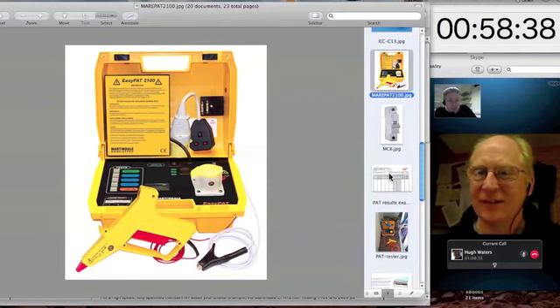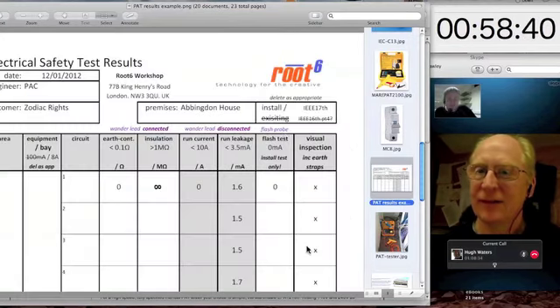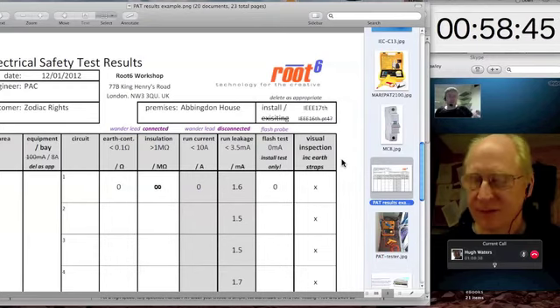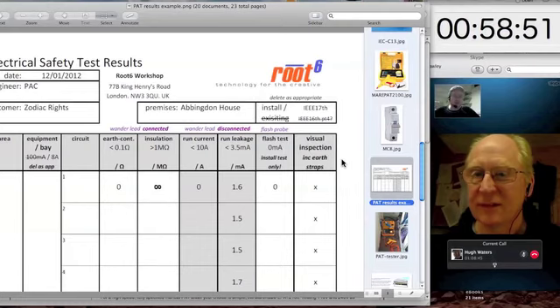And then the last test I have on the sheet that I expect the engineer to do is a visual inspection, to look at the end of the cable to make sure the connector isn't about to fall apart, and to inspect the earth straps that we run between the bays. And at this point, it's worth mentioning that the safest and the best build is one where you've got multiple paths back to earth.